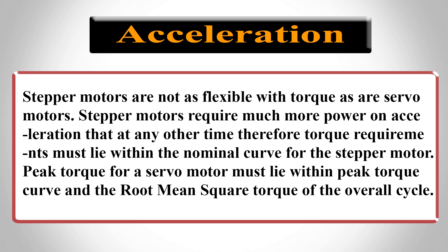Acceleration: Stepper motors are not as flexible with torque as are servo motors. Stepper motors require much more power on acceleration than at any other time; therefore torque requirements must lie within the nominal curve for the stepper motor. Peak torque for a servo motor must lie within the peak torque curve and the root mean square torque of the overall cycle.